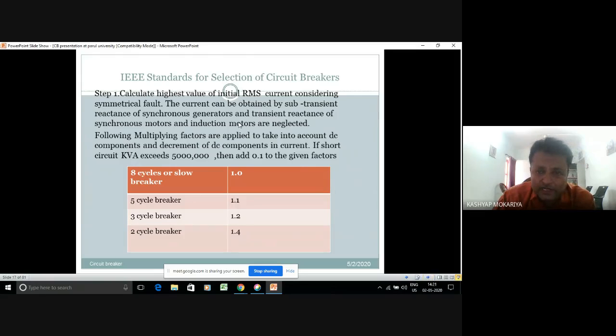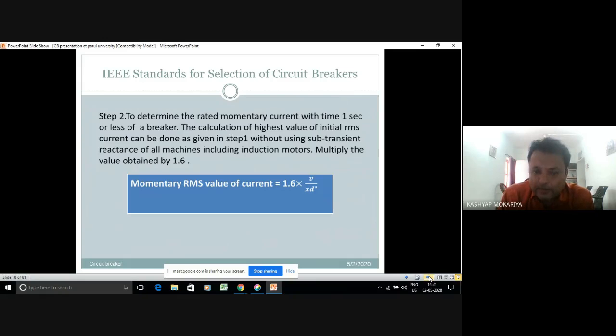Calculate the highest value of initial RMS current considering symmetrical fault. The current can be obtained by the subtransient reactance of the synchronous generator and the transient reactance of motors, and induction motors are neglected. The following multiplying factors are applied to take the DC components into account. So I'll go directly to the example. To determine the rated momentary current with time 1 second or less of the breaker, the calculation of the highest value of initial RMS current can be done as given in step 1 without using the subtransient reactance of all machines, including induction motors, and multiply that value by 1.6 according to the IEEE.